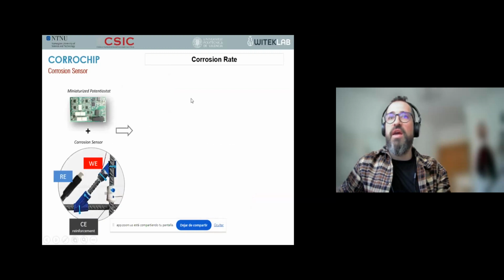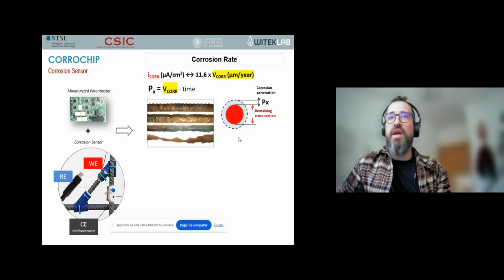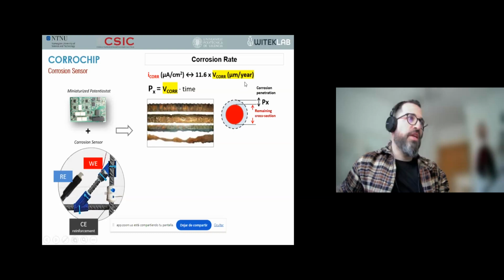What are the parameters obtained with the sensor? The main one is corrosion rate. This is a parameter of great importance as it expresses the rebar section loss per unit of time, usually in micrometers per year. It is also expressed in terms of current, because they are equivalent. Normally we work in terms of current, in microamps per square centimeter. So from the corrosion rate, the section loss of reinforcement for a specific period of time can be determined with that expression.